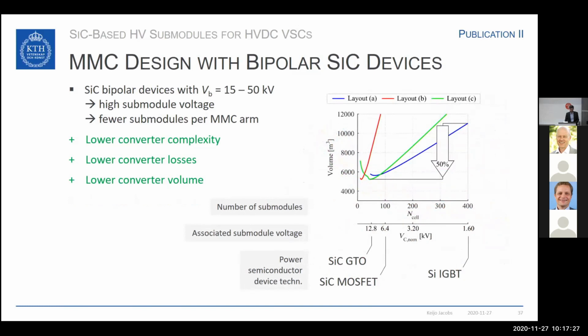For example, if you would design a converter with 400 submodules, then you would choose a submodule voltage of 1.6 kilovolts for the test case. And this would mean we would use silicon IGBTs. However, if we want to design the converter with 50 submodules, you would use a submodule voltage of 12.8 kilovolts. And this would mean we would choose a silicon carbide GTO. As you can see here in the graph, there is a significant potential for volume reduction, here up to 50%.